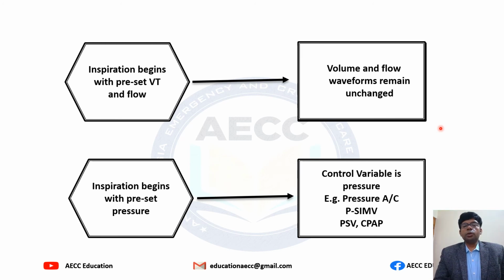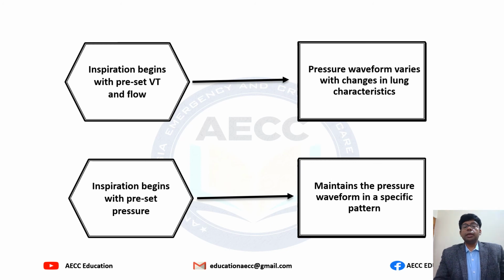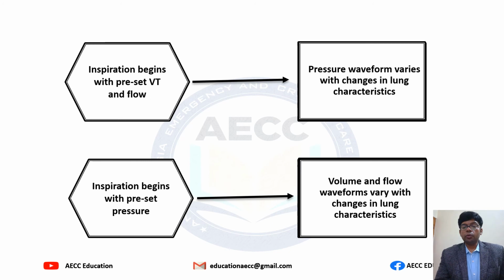In the volume control ventilation, the pressure waveform will change according to the lung characteristics, but the volume or flow waveform remains unchanged. In case of the pressure control ventilation, the pressure waveform remains maintained in a specific pattern, but the volume and flow waveforms vary with change in the lung characteristics.